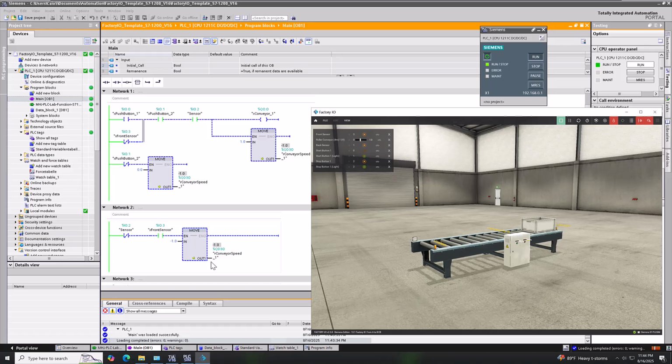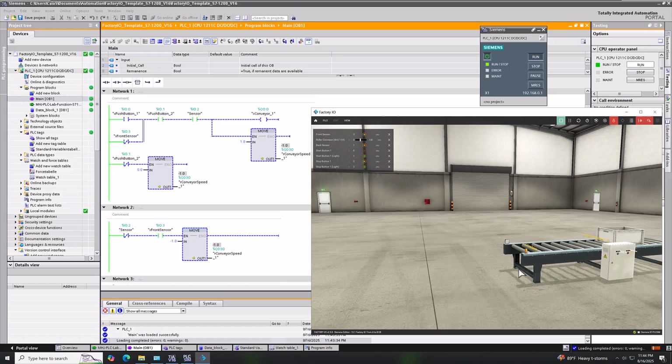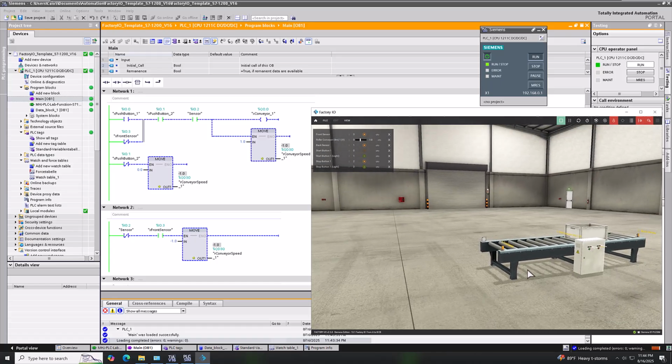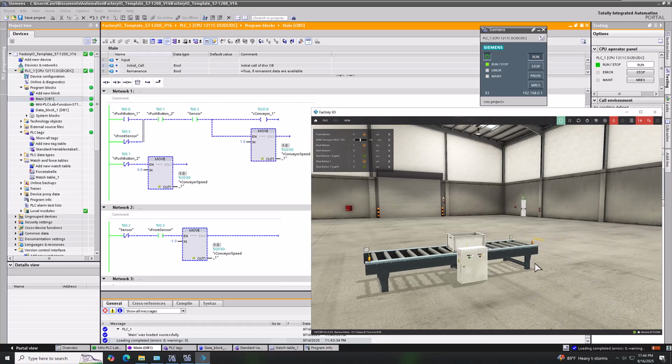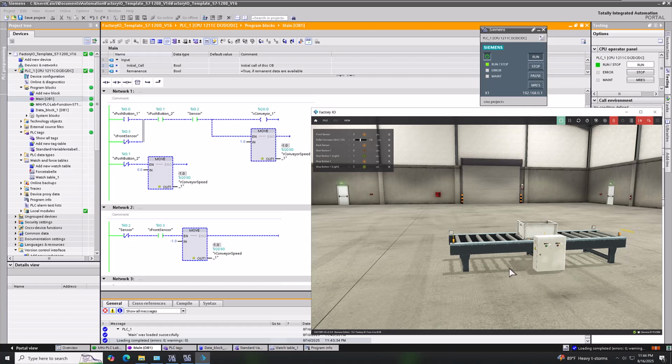And it's hitting the... Okay, well, it did hit the photo eye. But it's probably an alignment issue. I think I moved the carton or something. But we can adjust that. Let's see, this is D. So we just need to make sure our photo eyes are lined up better. That's all. Let's just make sure this bottom section works.